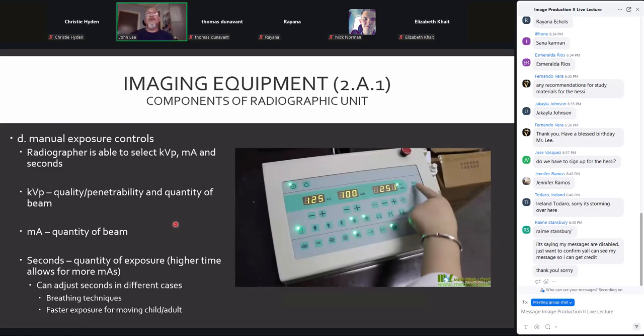Your manual exposure controls are also on the control panel. These are for our kV, our mA, and our seconds. Now, when we look at the circuit diagram, you may understand this a little bit better, but kV and mA are merely labels. Okay. When we adjust and manipulate the kV, we're manipulating what's going to go through the X-ray tube, but we're actually changing voltage in the circuit. When we adjust our mA, we're changing the amount of current that's flowing through the filament. And as I told you on the prior slide, that current is measured in amperes. The milliamperes is what's going to be flowing from cathode to anode in the X-ray tube, not what flows through the filament.